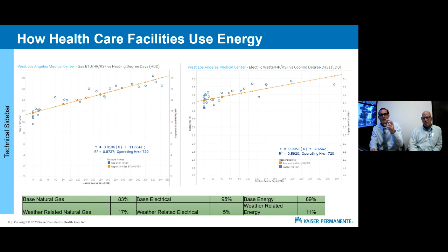So for this hospital you've been seeing in this example, base natural gas is 83% of the natural gas consumption. Base electrical consumption is 95% of the consumption. Altogether, the base energy is about 90%, or 89%, of that hospital's use. Only 11% of the hospital's energy use is actually weather related.